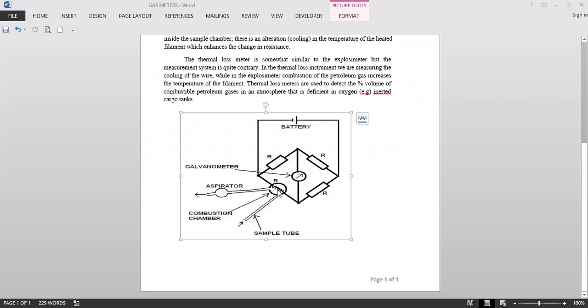R1 by R2 is not equal to R3 by R4 because on the R3 there is a sensitive filament which is non-catalytic which is placed. When the hydrocarbon gases pass through this, that will change the resistance and that will be measured on the galvanometer. So this is the working principle and the use of a tank scope.